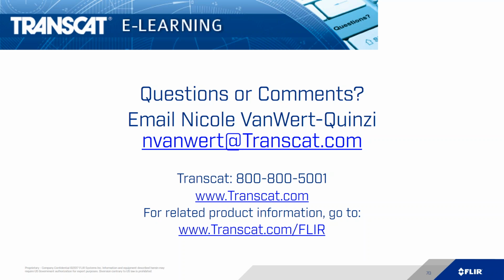Okay, can you discuss IR camera calibration? So infrared cameras, when we build an infrared camera, every detector is a unique detector, meaning there are no exact detectors alike. So when we get a detector and put it in an infrared camera, we see how it responds to a known temperature source. Once we see how it responds, we calibrate that to react to that temperature in that camera to the intensity that we're seeing. And this is good for 1 year.